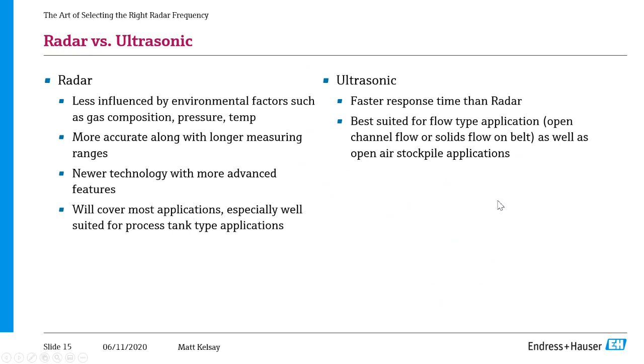Radars are more accurate, and they often have much longer measuring ranges as well, so they cover a wider basket of applications. Many of the new technological advances are going into radars, so you'll see a lot more features and benefits, a lot of advancements in radar technology as opposed to ultrasonic in our basket as well as others. And I would say for radar devices, we'll cover most applications. Probably in the 85% range of non-contacting devices are going to be radar devices, especially in process tank type applications. So anything where you're enclosed in a tank is especially well suited for a radar device.